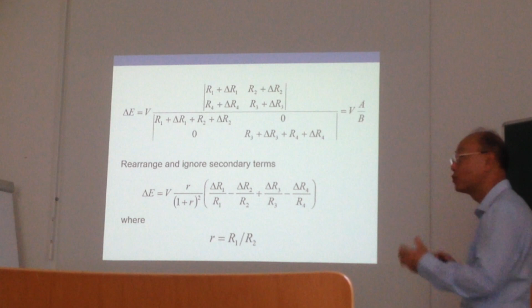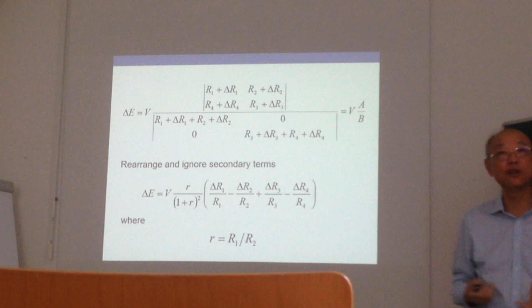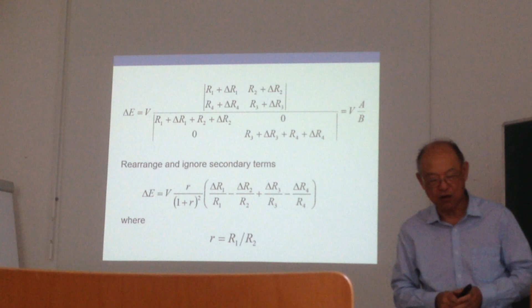But for strain, if you align the system so that when deformation occurs one side increases and the other decreases, the real strain measurement doubles its resolution. So it's a very good system that can be used to minimize or offset the temperature effect with a Wheatstone bridge — a technique we use often.